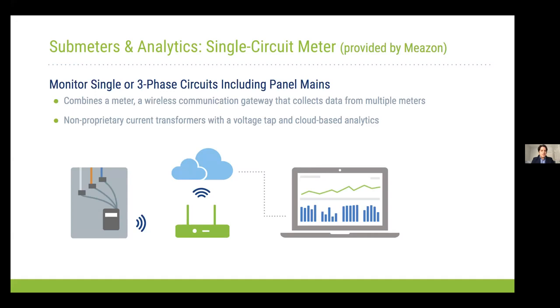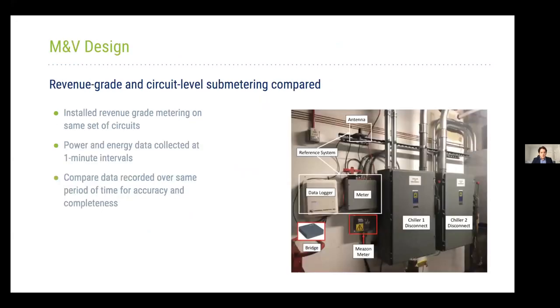Let me talk a little bit about the measurement verification plan. We wanted to make sure we were comparing apples to apples, as close as we could. This comparison was side-by-side, and the image shows two chiller disconnects, chiller 1 and chiller 2. We installed the meters in the same circuits so we were getting the same type of information, using the same period and the same time intervals, trying to make sure everything was the same.